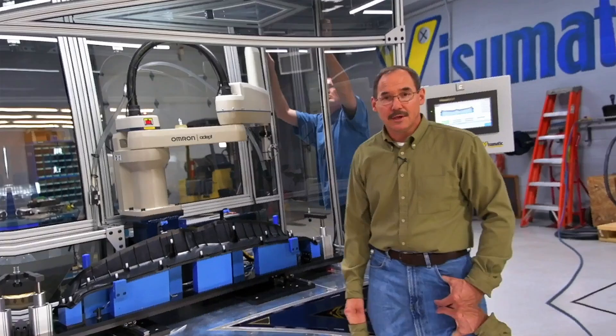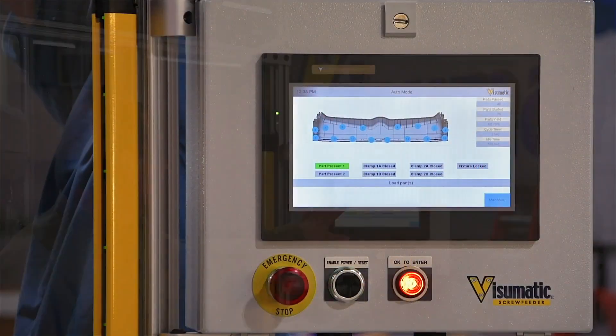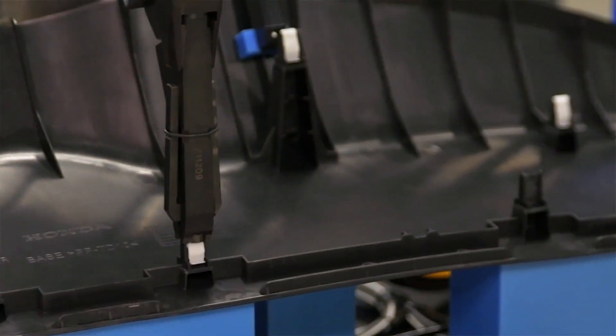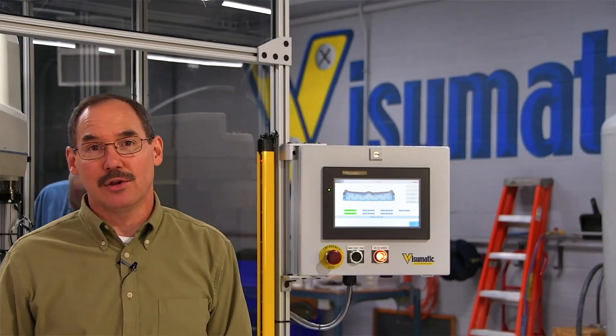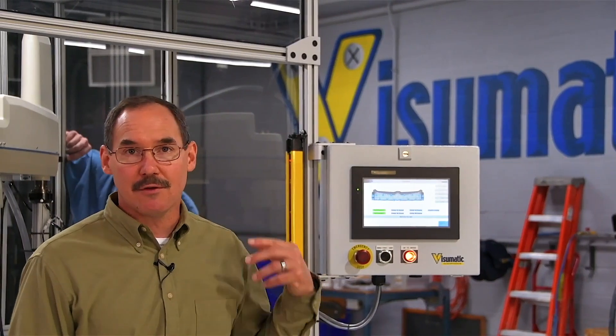We've got a Visumatic standard VIM 700 clip insertion module mounted directly to the robot quill for our vertical-down application. This machine uses an HMI with a graphical display showing a 3D version of the part along with each clip insertion point. These indicators change state during operation — green for good, yellow for an error, and red for bad — and the PLC keeps track of all that and gives a report when the cycle is complete.